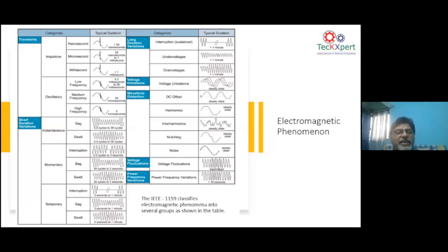Similarly, when it comes to an oscillation, it has another aspect, which is the frequency. An impulse will have only a magnitude, the rate of rise, and the drooping. But an oscillatory transient will also have a frequency over that. And again, these sorts of fluctuations are all short duration. As you see, it's all in milliseconds or microseconds, so that it remains only in a half cycle or a quarter of your wave cycle, because your wave cycle is 20 milliseconds. So transients can be only in a half cycle or quarter of a cycle.